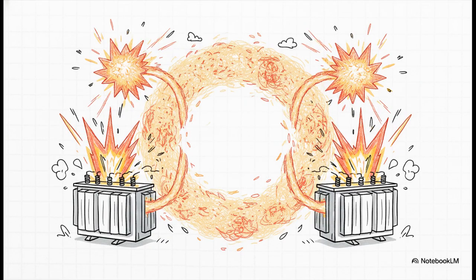The answer is a hard no. Absolutely not. Even though they both have delta and star windings, their vector groups are different, which means their phase shifts are entirely different. If you try paralleling transformers with mismatched phase angles, it drives a massive, destructive circulating current right between the two units. We're talking about forces that can completely destroy both transformers in a really spectacular fashion. Vector group matching is absolutely a hard rule. It is definitely not a polite suggestion.